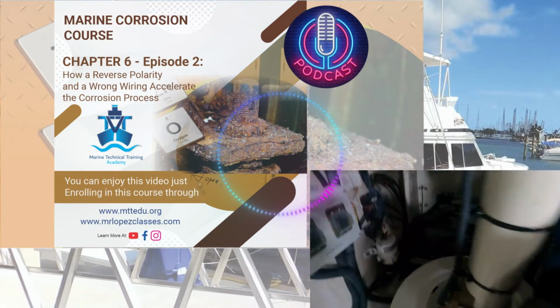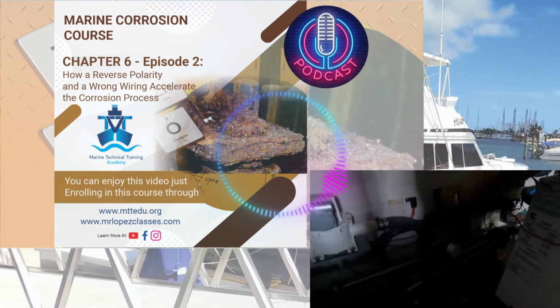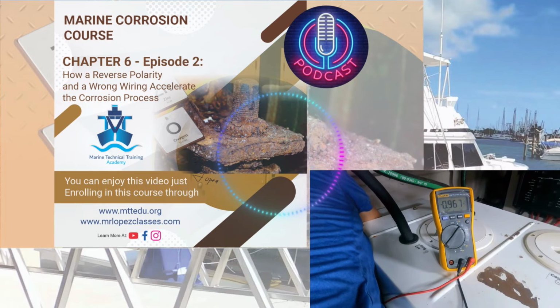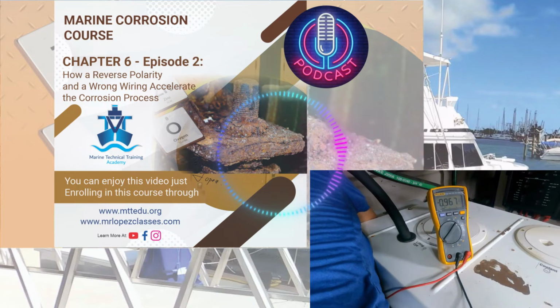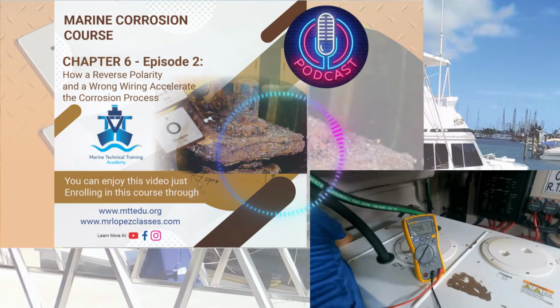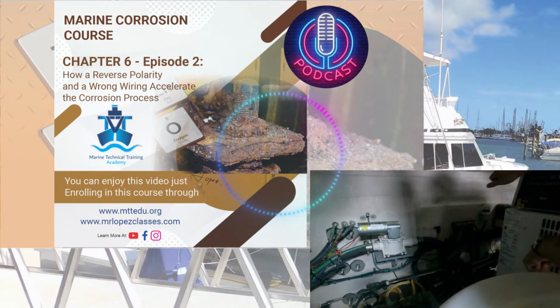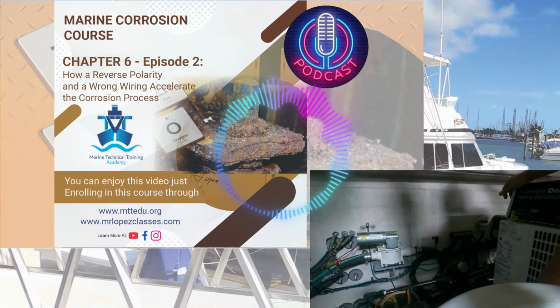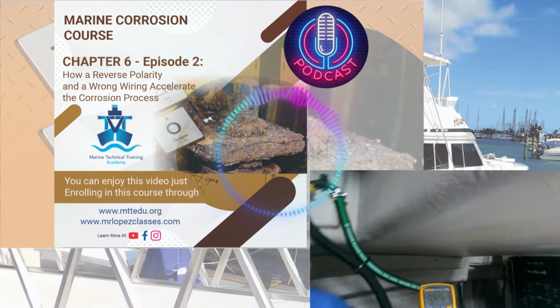Right now, I have a return of 3 amps, 5 amps in the neutral bus bar. I have a current in the neutral bus bar because those outlets are switched. And what happens if that neutral bus bar is connected with the ground bus bar?